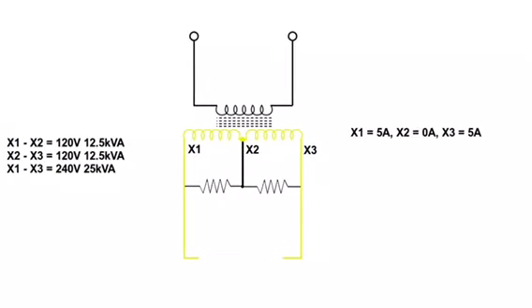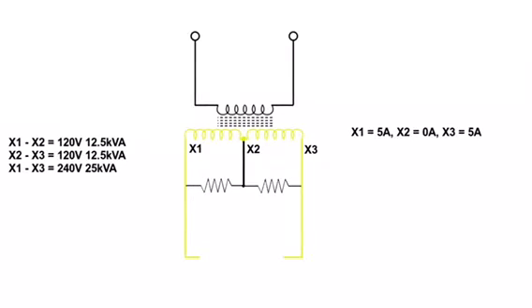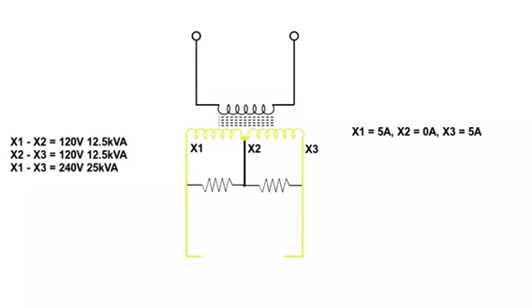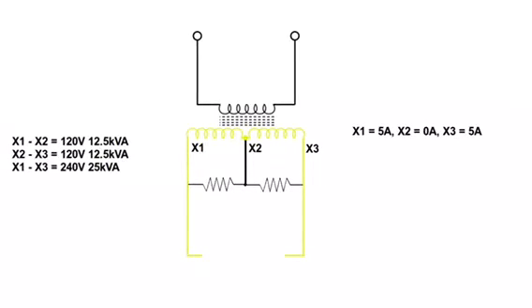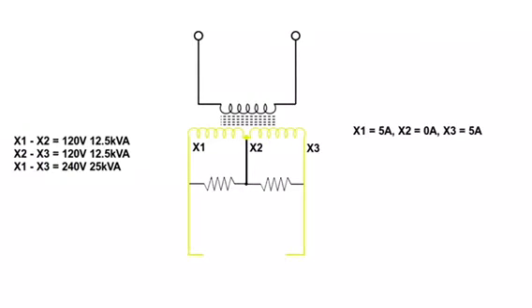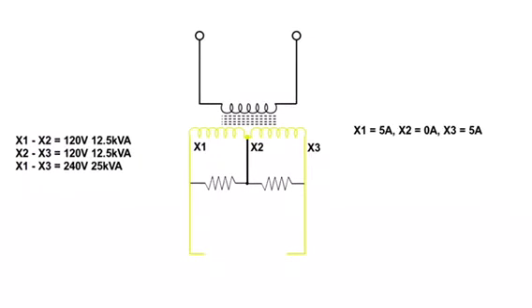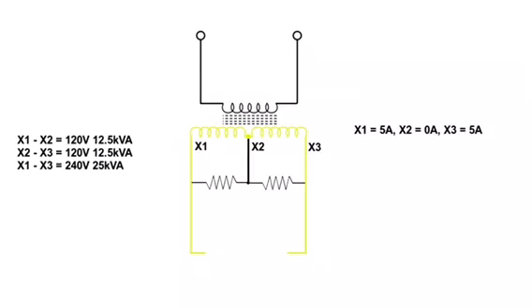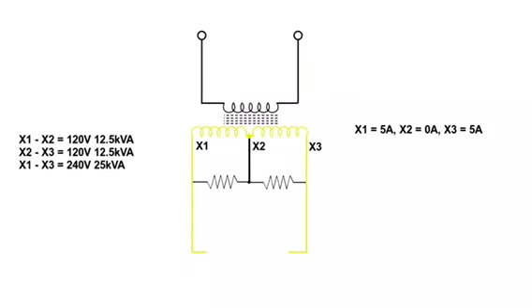So if we take our amp probe and go to X1, we will see 5 amps going across that X1 terminal. If we move the amp probe over to X2, it should be 0. In real world conditions, you might see 1 amp or so there. If we move that amp probe over to X3, we also see 5 amps, and that's because we have our two loads connected in series. So you've got 120 volts on the left, 120 volts on the right. You add those two together, and it gives you a total of 240 volts. The transformer is outputting 240 volts, so the total amps that the transformer sees is 5 amps.